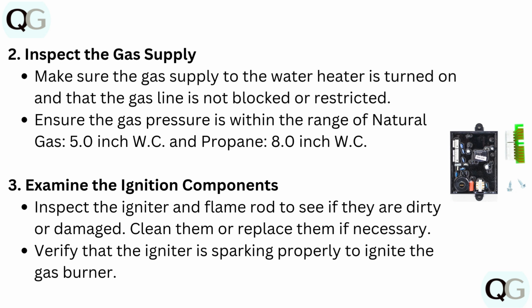2. Inspect the gas supply. Make sure the gas supply to the water heater is turned on and that the gas line is not blocked or restricted. Ensure the gas pressure is within the range of natural gas, 5.0-inch WC, and propane, 8.0-inch WC.